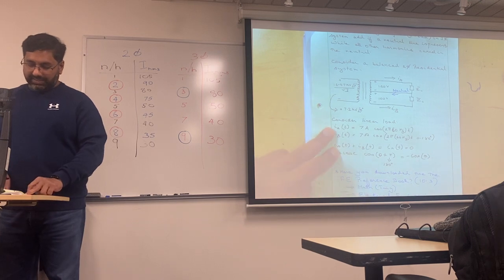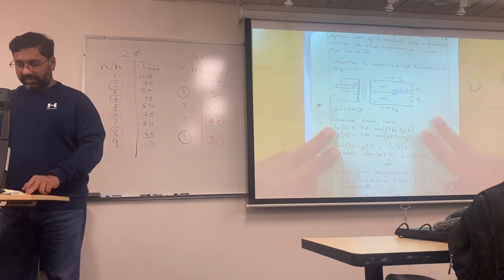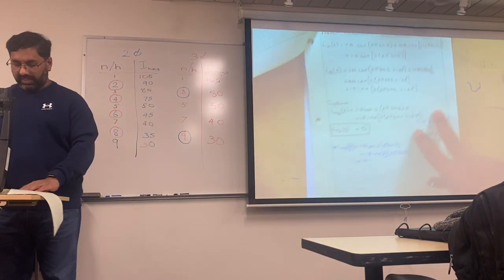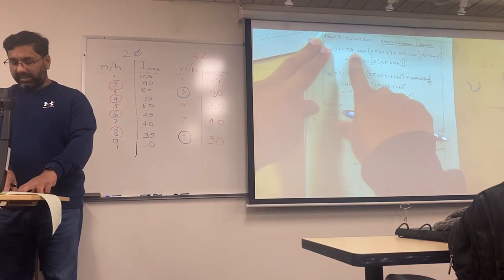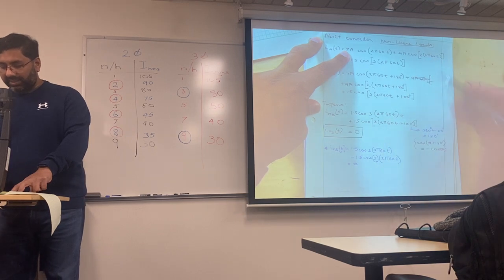I then skipped and used... I then considered a non-linear load where I used 7A and I still had the 60 Hertz, a 4 ampere for the 120 Hertz. And how I did the 120 Hertz is 2 times 60.